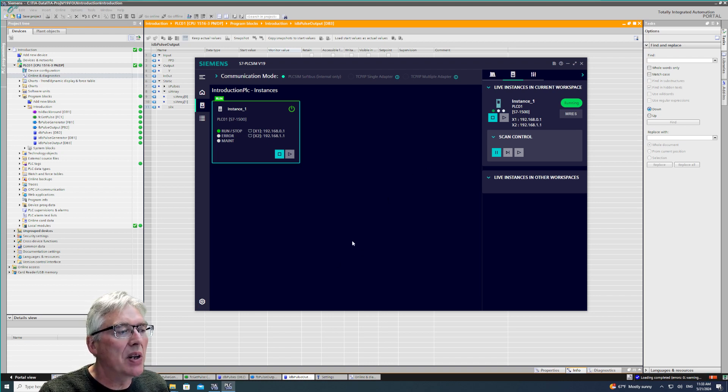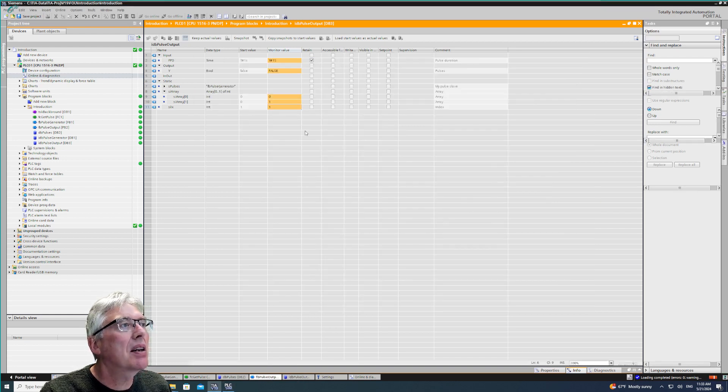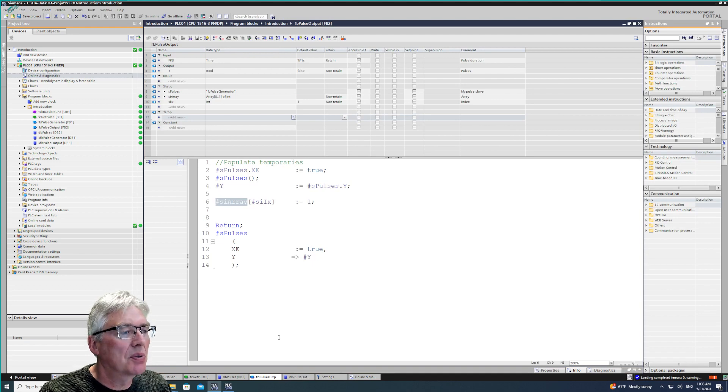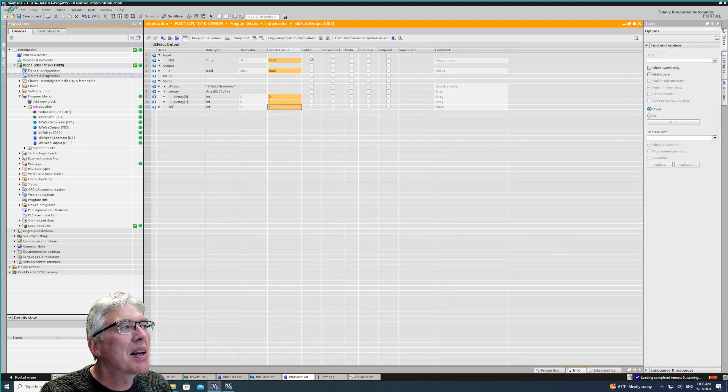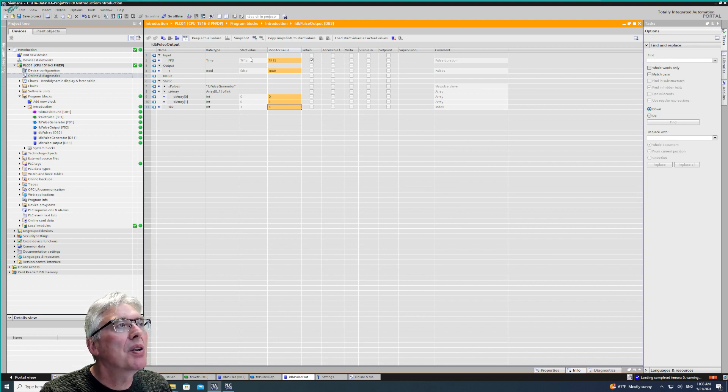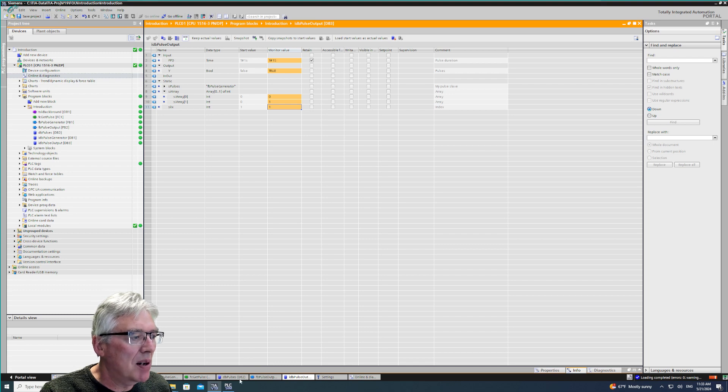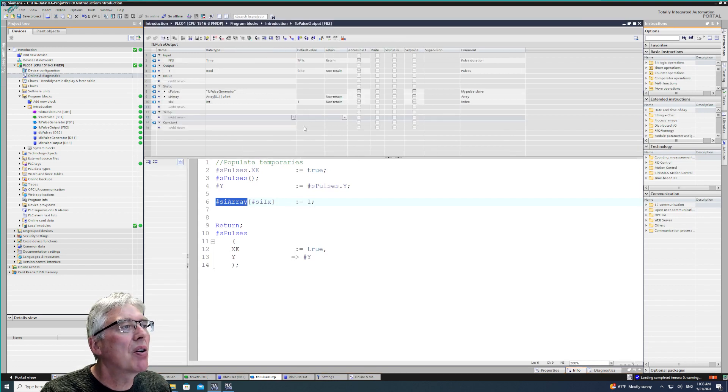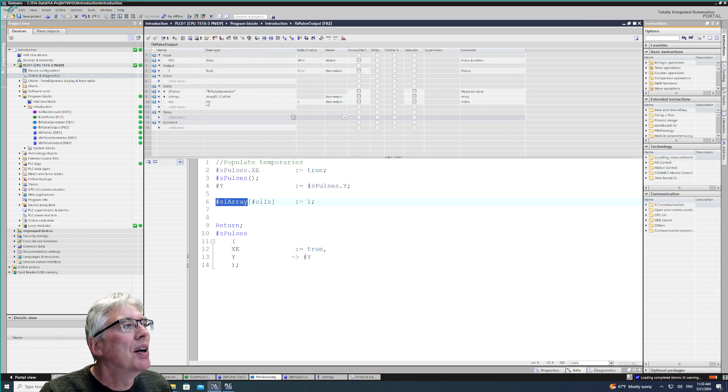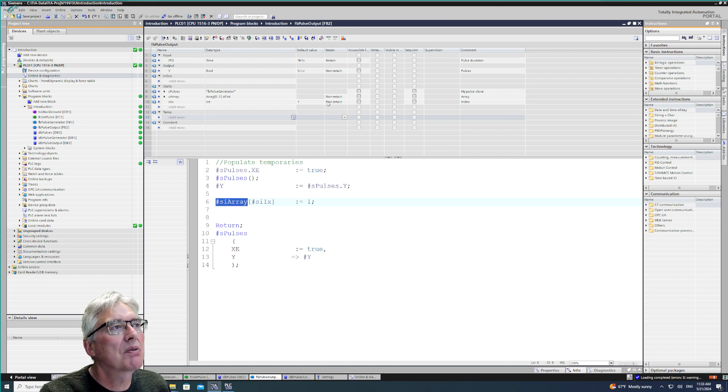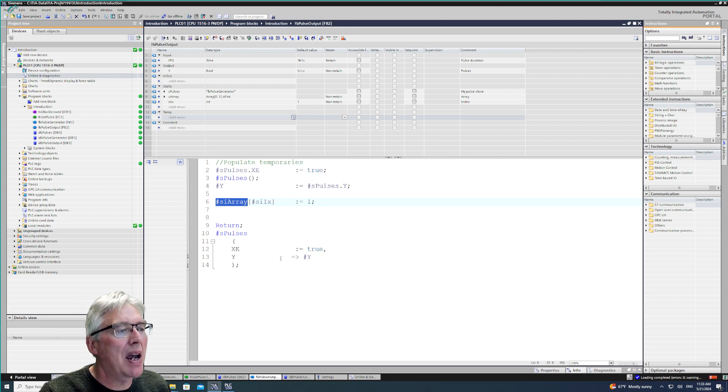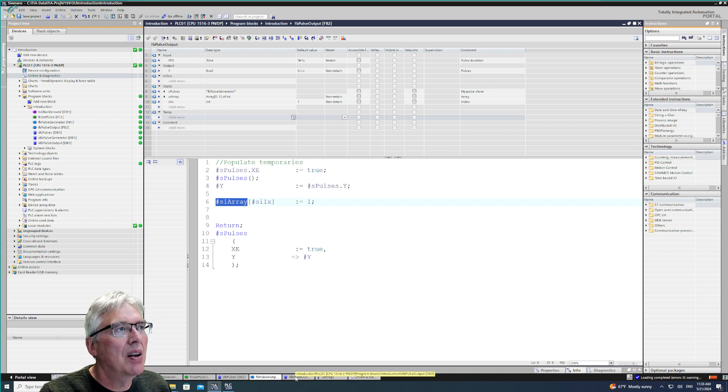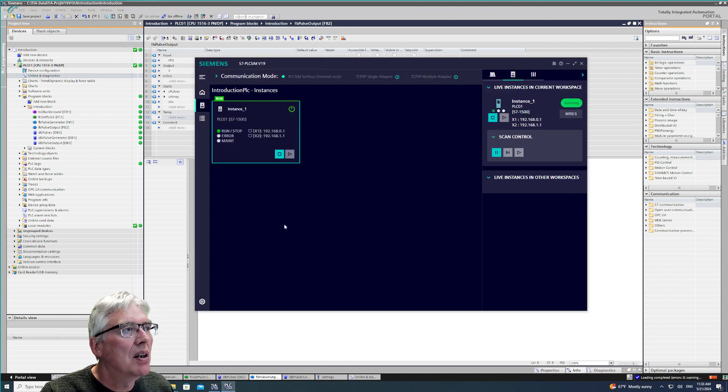Well, what I can do is start my CPU running. It's probably not going to run, it's going to go back to stopped because the error is still there, or is it? It shouldn't be, maybe it's not because it's running. Let's look at my IDB again. My index is back to one because what I didn't do is my function data block. This one in my function block is not retained, that one is retained, but this one is not retained. So when I restart the CPU it gets the default value back. That was nice, but if I had it retained it would keep the value, then we'd get an error when I restarted. But now I'm fine, I didn't correct the error, I corrected the error just by restarting the CPU.